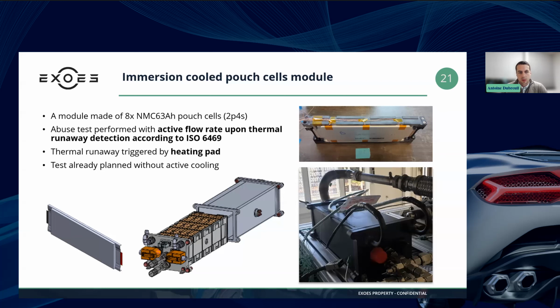For this, we follow the ISO 6469 standard, which gives us a number of detection criteria that we can use to determine whether or not a thermal runaway has been triggered. So upon detection, pump flow will be activated. We already have a plan to run the same test without active cooling. This one will be in the coming weeks, but at least we can share these results with you today.